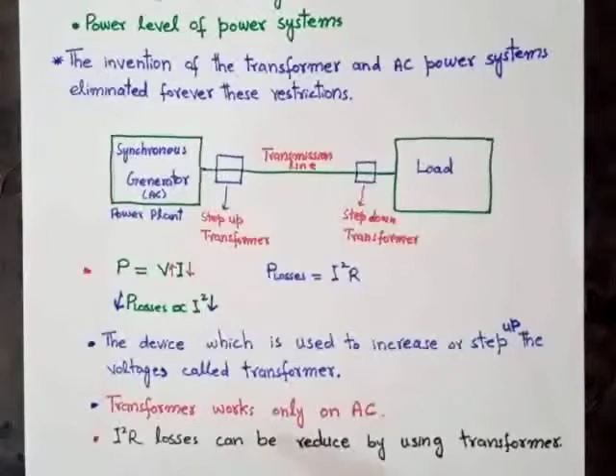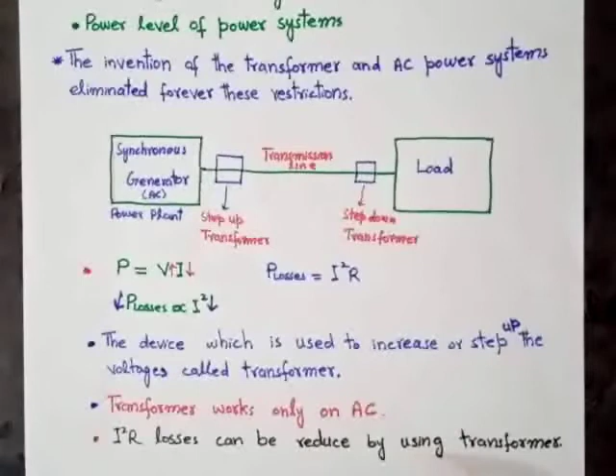The overall conclusion is that we can reduce the I square R losses by using a transformer. Without a transformer, the voltages are very low and the current is high. If the current is high, then the losses will be high as well. After using the transformer, the value of the voltage will be more. When the voltage is more, the current will be less for the same amount of power. When the current is less, the losses will be less as well. That's why I square R losses can be reduced by using a transformer.